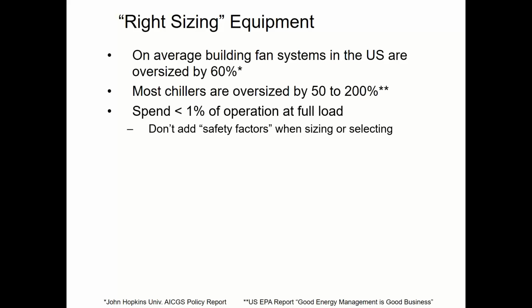Inputs meaning, what kind of windows do you have? What kind of insulation do you have? All those questions when you're answering them in your software. If you guess, and you guess conservatively, i.e. adding safety factors on all of your inputs, that really magnifies the final answer. And then most of you take the final answer and round up anyway. You add another safety factor. So at least put very pure inputs in and guess aggressively if you have to guess. And then at the end, if you need to add a safety factor or round up to the next whole size, that's one thing. But you're putting safety factors on the inputs and on the outputs, and it's causing a mess, meaning a lot of stuff is double sized.